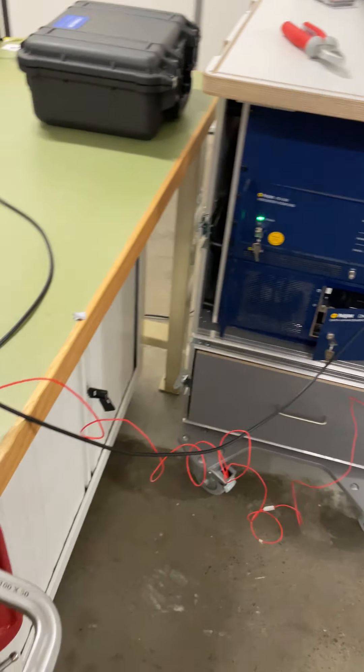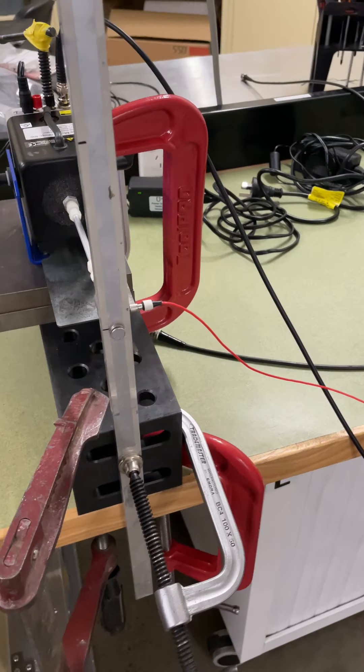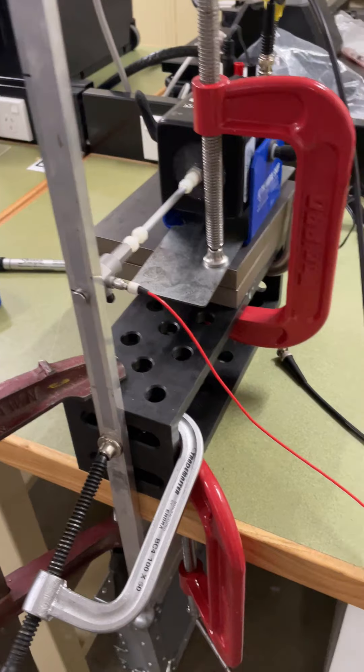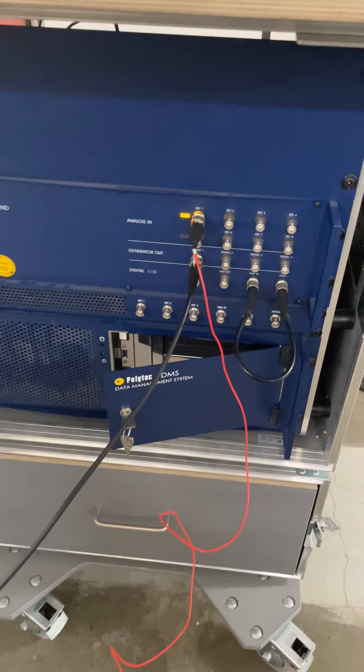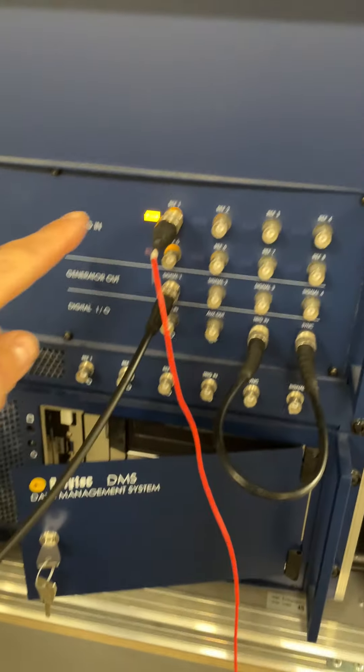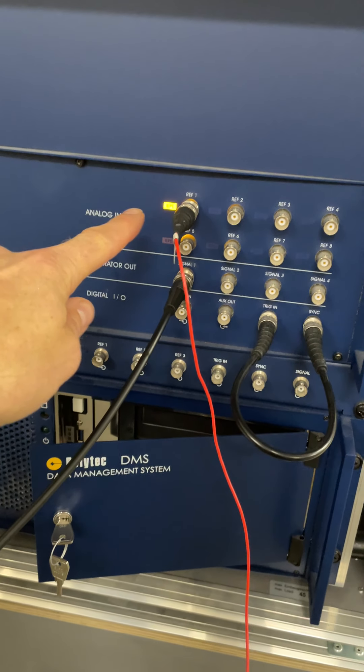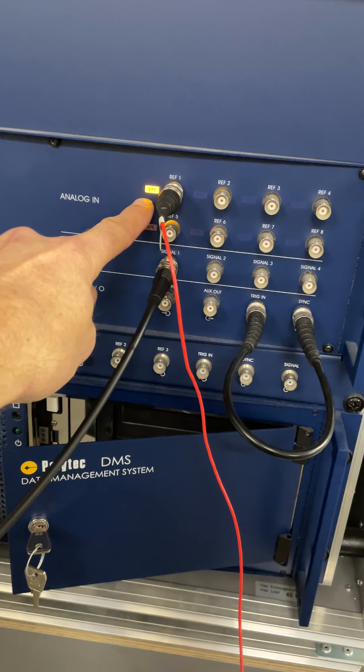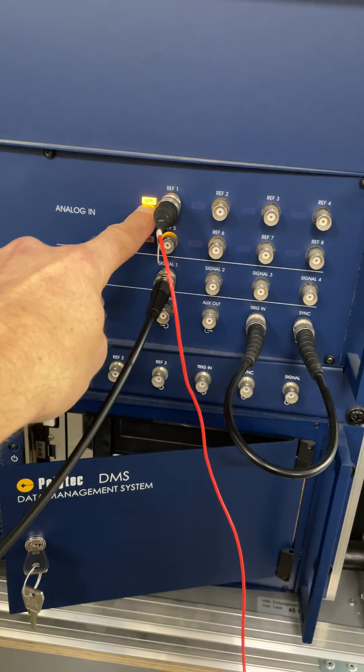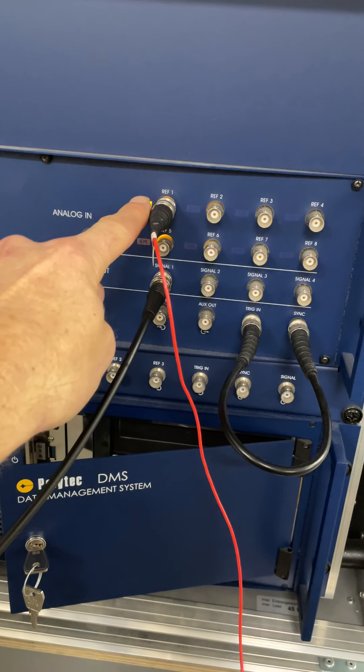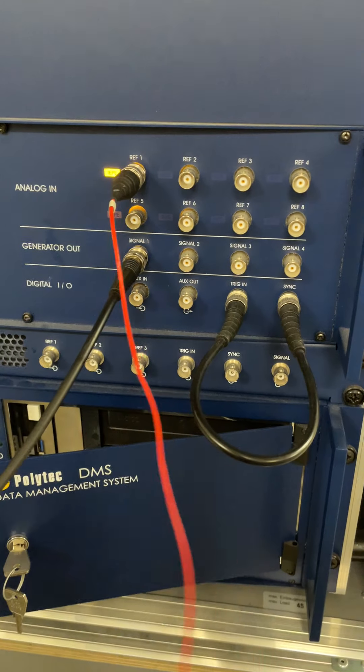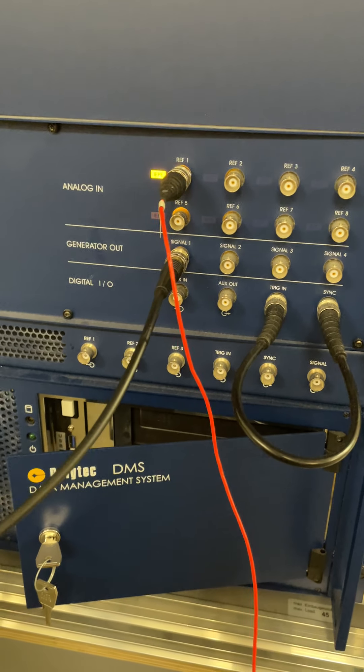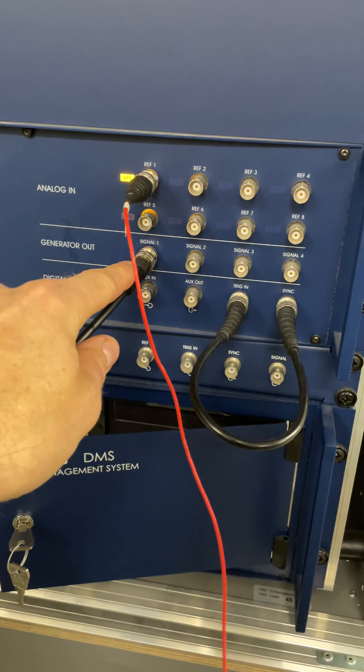The force transducer is an IEP type of transducer and is connected over a cable into the controller of the laser vibrometer. You can see the IEP light, integrated electronics piezoelectric light, is currently illuminated because this is providing power for the transducer for the signal conditioning which is within the transducer.